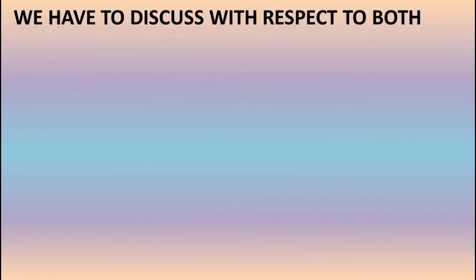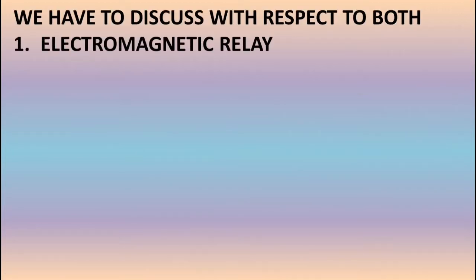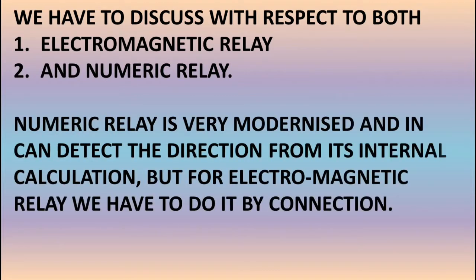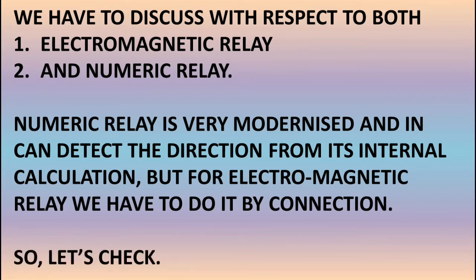We have to discuss with respect to both the electromagnetic relay and the numeric relay. The numeric relay is very modernized and can detect direction from its internal calculation. But the ancient electromagnetic relay couldn't do that, so we have to achieve it by altering the CT connection.